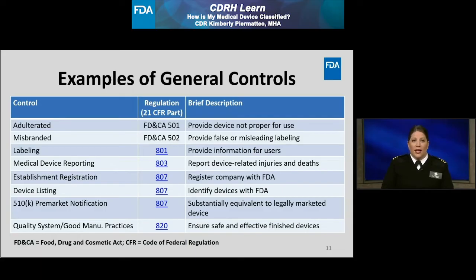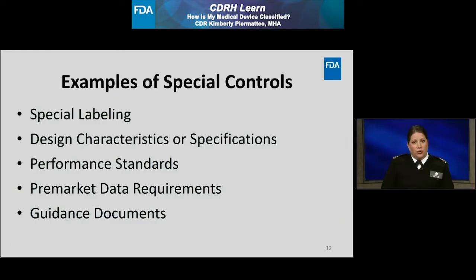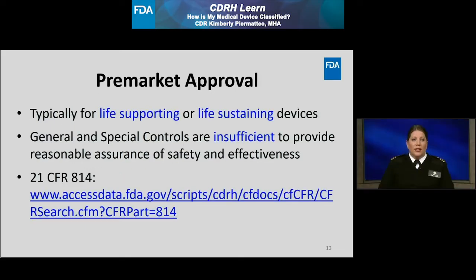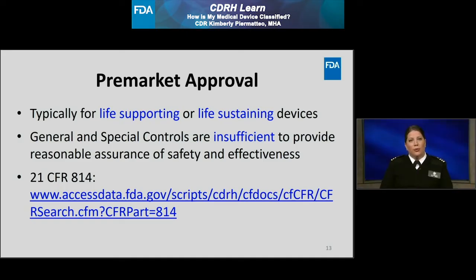Class 2 devices may also be subject to special controls, which would be identified by the FDA and may include special labeling requirements, design characteristics or specifications, or compliance with a particular performance standard or testing. There may also be a special controls guidance document for a particular device type outlining any of these. Class 3 devices are typically life-supporting or life-sustaining. Therefore, due to the level of risk associated with Class 3 devices, general and special controls alone are insufficient to assure their safety and effectiveness.